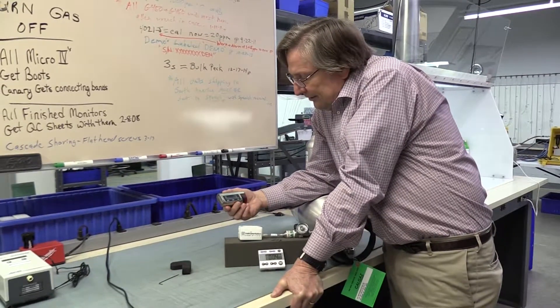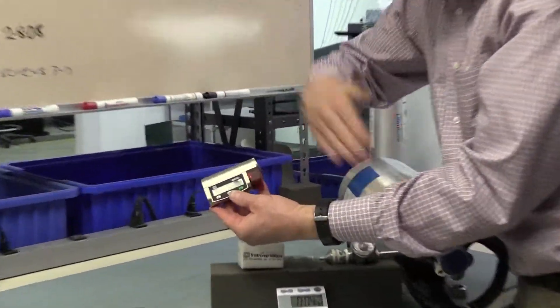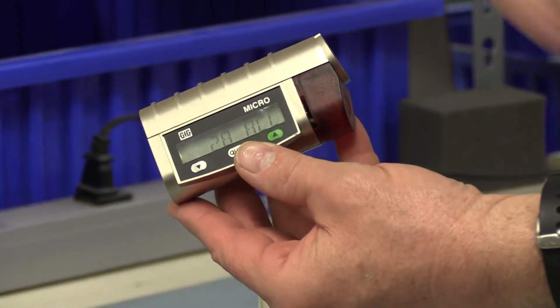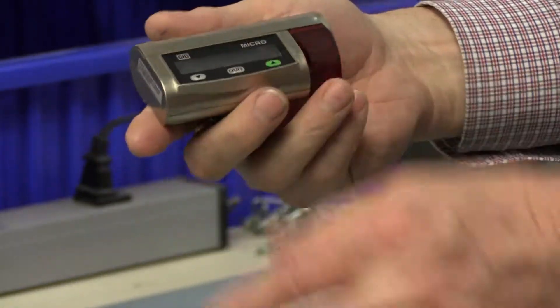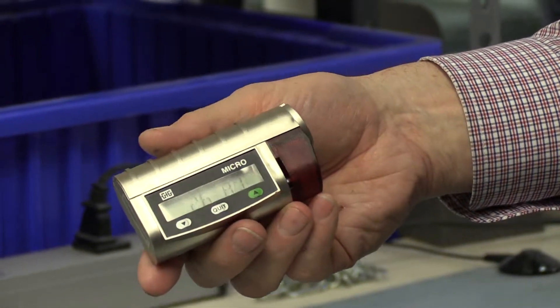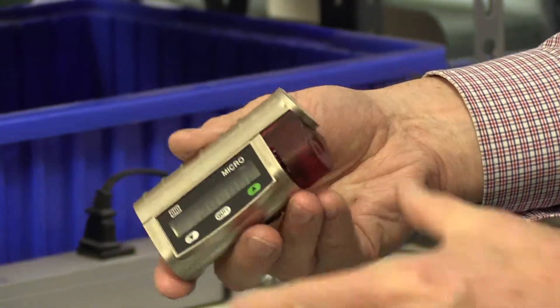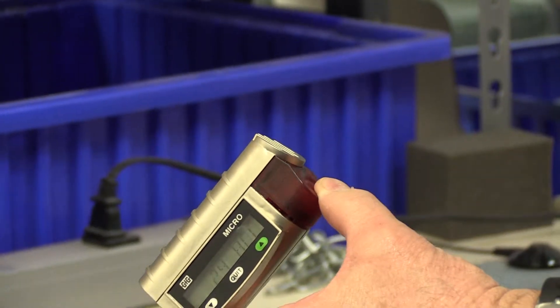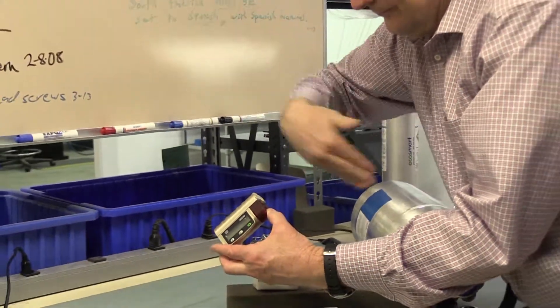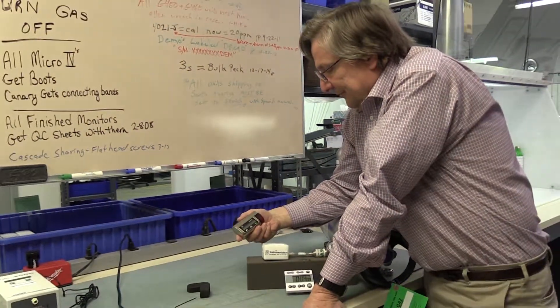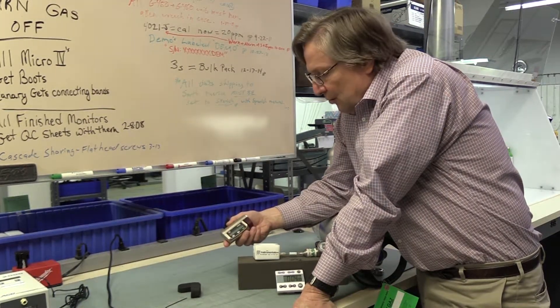And if you want, you can fan the sensor a little bit with fresh air. That will speed up the process. You actually should not blow on the sensor to get it to clear down a little bit more quickly, because the moisture in your exhaled breath actually has an effect on the sensor reading. So it's better if you just fan the sensor a little bit, or give it a few moments, and it's in the process of coming down. So I'm at 2.0, and there the alarm is now turned off. So that's all there is.